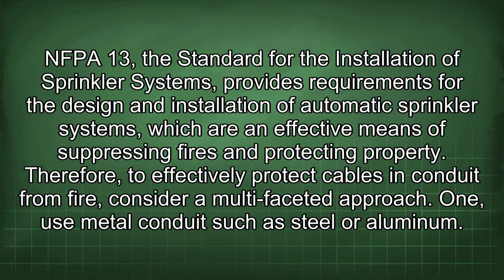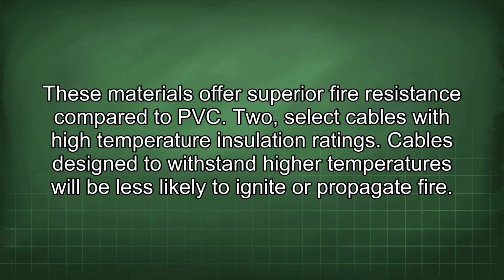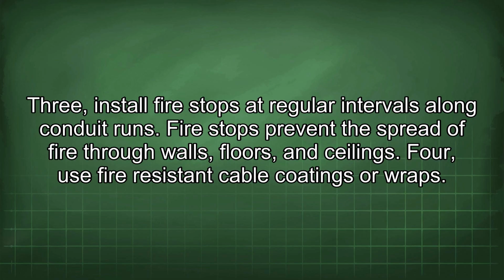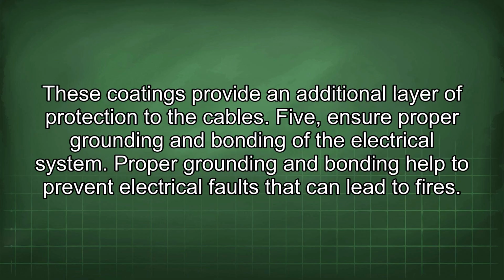Therefore, to effectively protect cables in conduit from fire, consider a multifaceted approach. 1. Use metal conduit such as steel or aluminum. These materials offer superior fire resistance compared to PVC. 2. Select cables with high temperature insulation ratings. Cables designed to withstand higher temperatures will be less likely to ignite or propagate fire. 3. Install fire stops at regular intervals along conduit runs. Fire stops prevent the spread of fire through walls, floors, and ceilings. 4. Use fire-resistant cable coatings or wraps. These coatings provide an additional layer of protection to the cables.